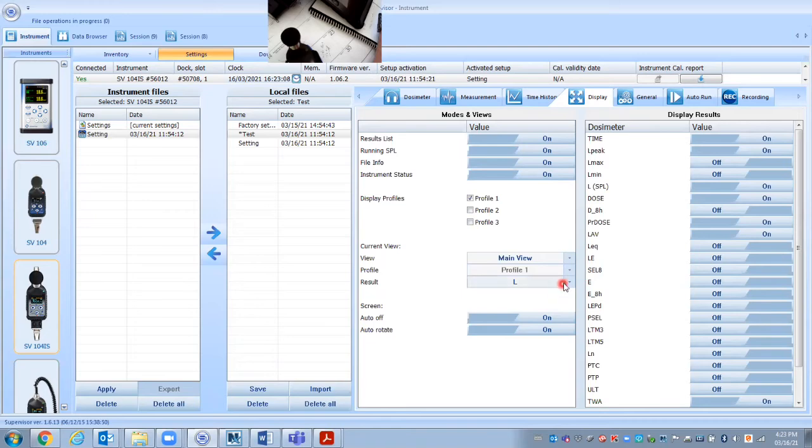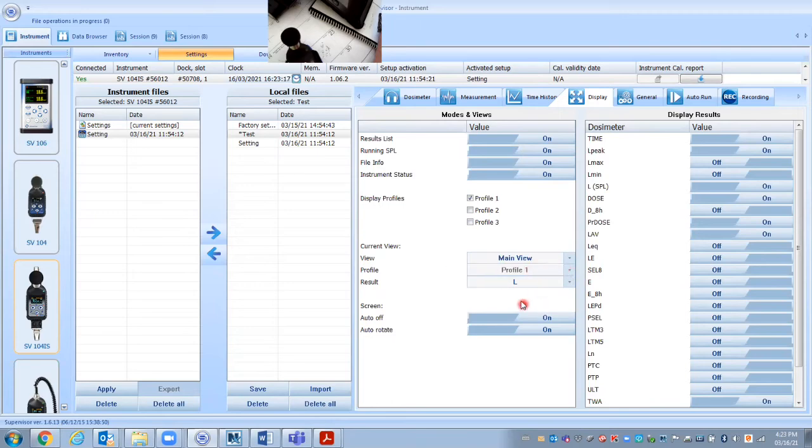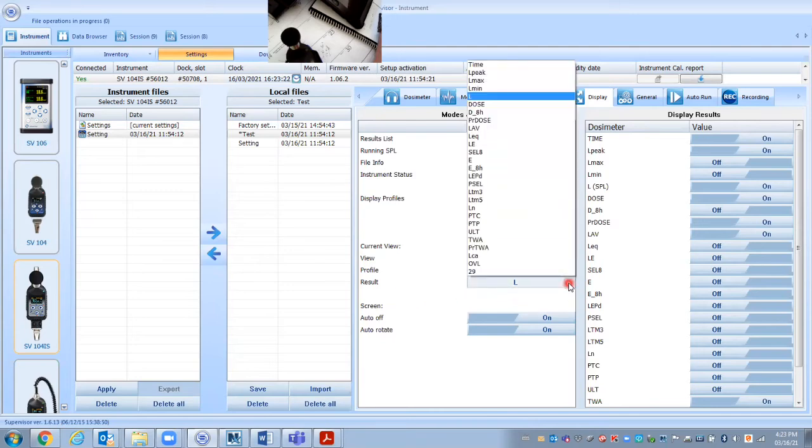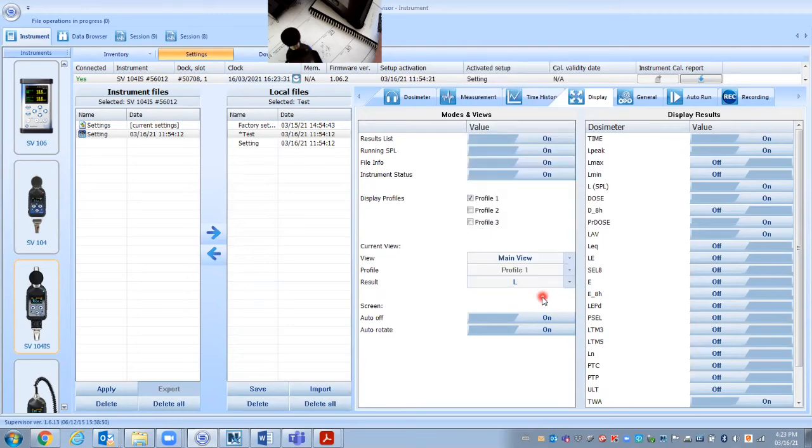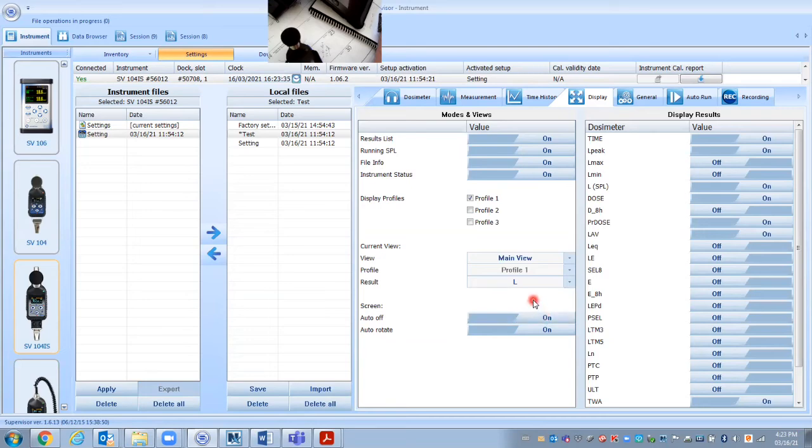These settings here, we want to have the main view is the first option under view. The profile we're using is only profile one. And L is basically the we want to see the sound. But there's other things we could look at other settings that you could look at, like dose or anything like that that you'd want to put in. But usually L for sound is usually the most common. Auto off if no buttons are pressed, if you have that turned on after a certain amount of time that will shut down and save the battery.